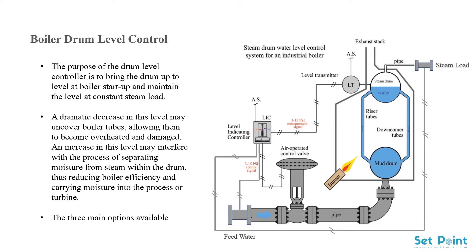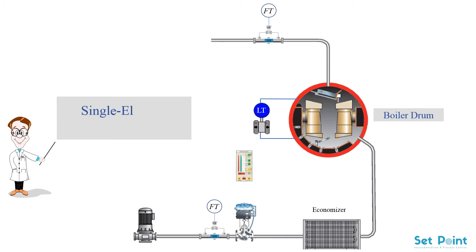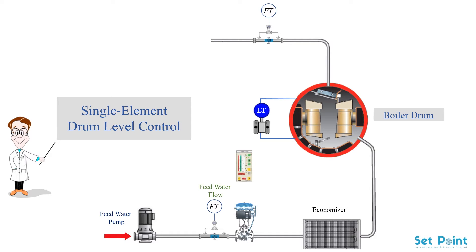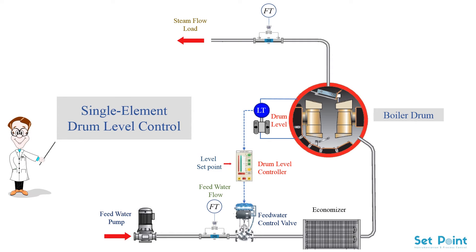The three main options available for drum level control are: single element drum level control. In this type of control mechanism, water is fed into the boiler drum through a single or multiple pipes and thus a single or multiple control valves. Only the water level in the drum is measured through a level transmitter and the information is sent to the controller. Based on the obtained information, it is compared to the set point and then control valves are manipulated in order to increase or decrease the flow rate of the water inside the boiler drum.